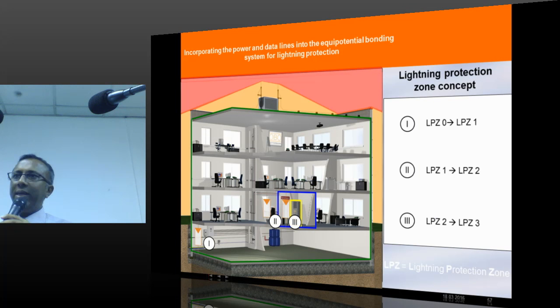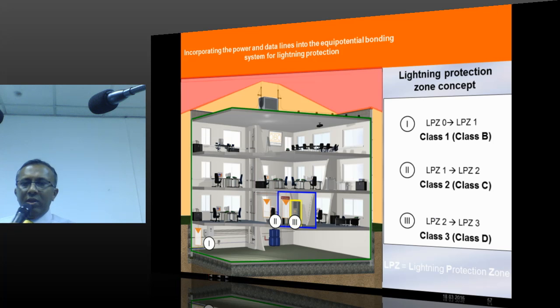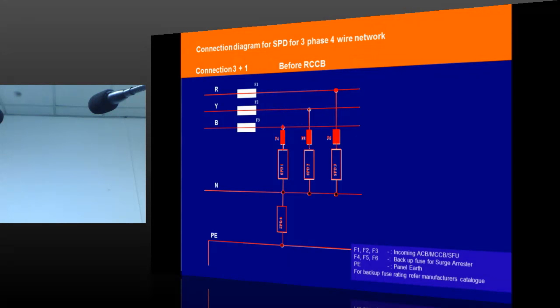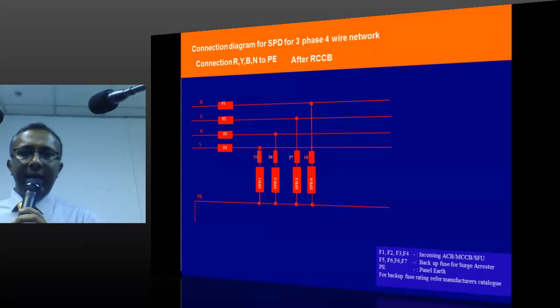So I skipped this slide also. Okay, the SPDs are called as class 1, but generally we used to call as class B, but class B is according to the old German standard, but according to IEC it is class 1, class 2 and class 3. Three kind of SPDs are required to reduce the transient voltage. So here a kind of a connection is explained. I skipped these two slides.